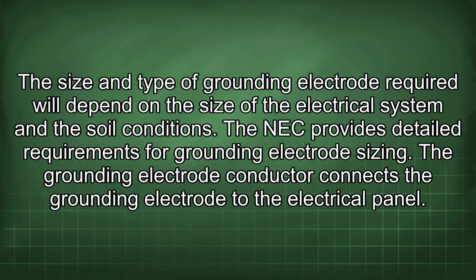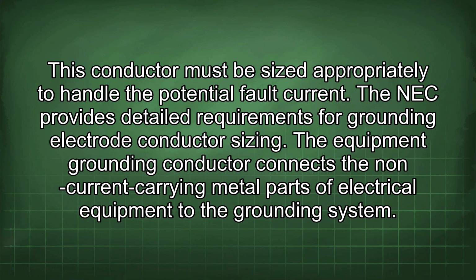The size and type of grounding electrode required will depend on the size of the electrical system and the soil conditions. The NEC provides detailed requirements for grounding electrode sizing. The grounding electrode conductor connects the grounding electrode to the electrical panel. This conductor must be sized appropriately to handle the potential fault current. The NEC provides detailed requirements for grounding electrode conductor sizing.